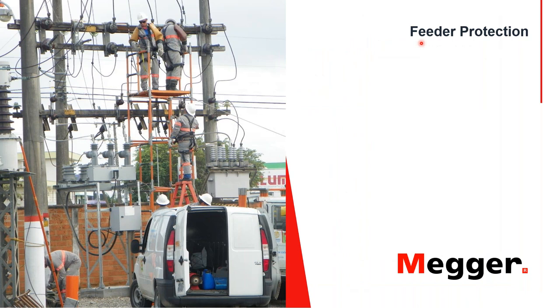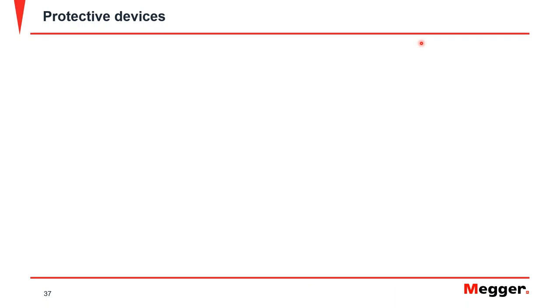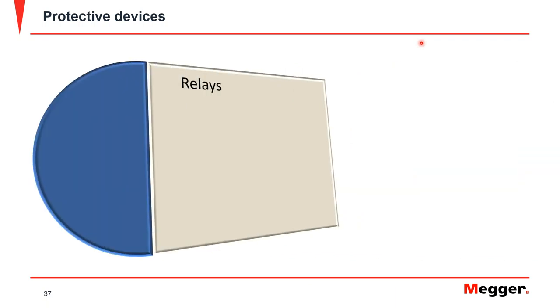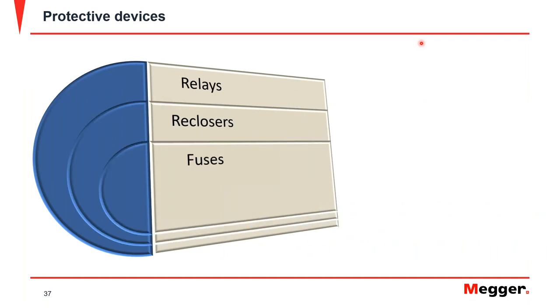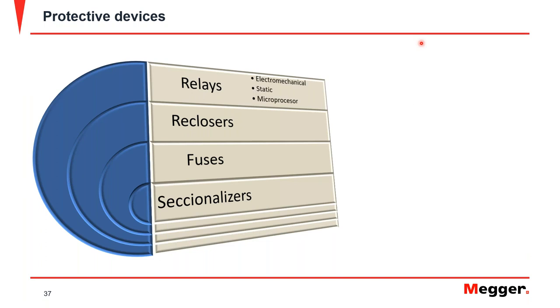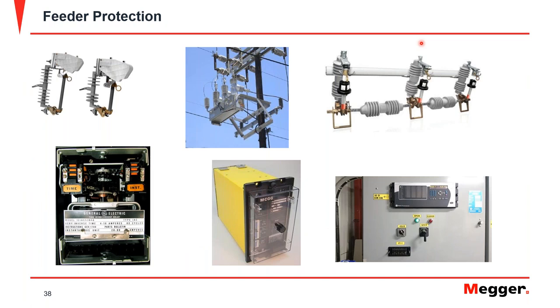When it comes to protective devices in feeders, we use relays, reclosers, fuses, and sectionalizers. Relays can be electromechanical, static, or microprocessor-based. Depending on location, you may find only electromechanical or mostly microprocessor relays, but most systems have a combination. Protection functions include instantaneous and time overcurrent for phase, neutral, ground, and negative sequence overcurrent — all connected to CTs. Voltage-related functions include under/overvoltage, ground overvoltage, and negative sequence overvoltage. Distance protection, frequency elements, power elements, and directional overcurrent relays are also used.